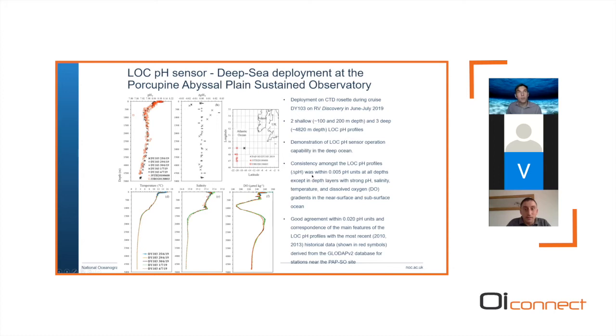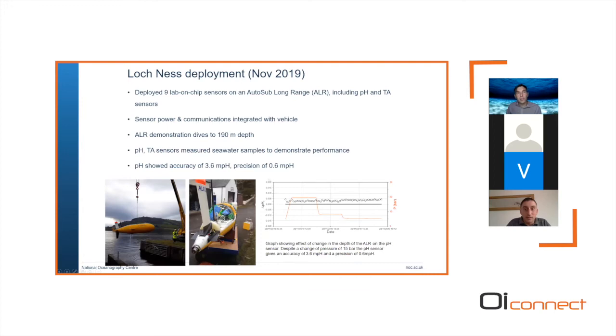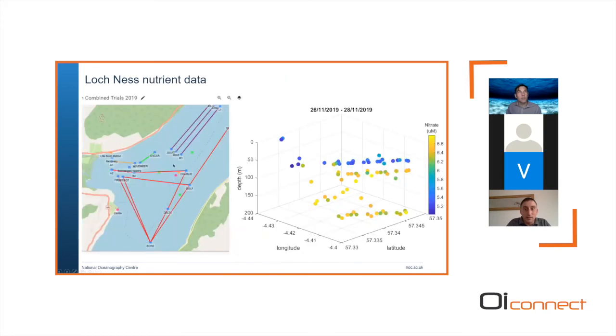So really, really positive. Here's some data using that system in Loch Ness. The salinity means that the pH sensor doesn't actually function. So we were measuring against a standard, but that enabled us to show that we had very good accuracy, 3.6 millipH, and a precision sub-millipH with that system. But here is some data from that deployment showing nitrate being measured in Loch Ness.